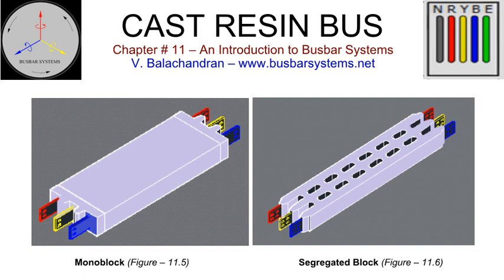The phase spacing at the exposed ends of the conductor, for terminations, increases with the increase in the rated voltage. Monoblock designs become expensive for rated voltage above 12 kV. Segregated block. In a segregated block design, it becomes economical to space the conductors apart, according to the rated voltage. Depending upon the fault withstand capability, tie connections are envisaged at predetermined spans. The 3 phases and the tie rods are cast together to form an integral piece.